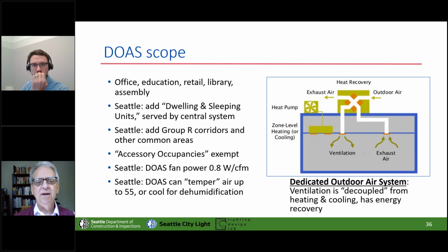So in Seattle, we add dwelling and sleeping units if they're a central system and not individual units. And we add the corridors and common areas between dwelling units. One bullet point there is that an accessory occupancy, which is defined in the building code as less than 10% of the floor area of a particular floor of a building, you don't have to do a separate DOAS if you've got, say, a big warehouse with a little office area in it.